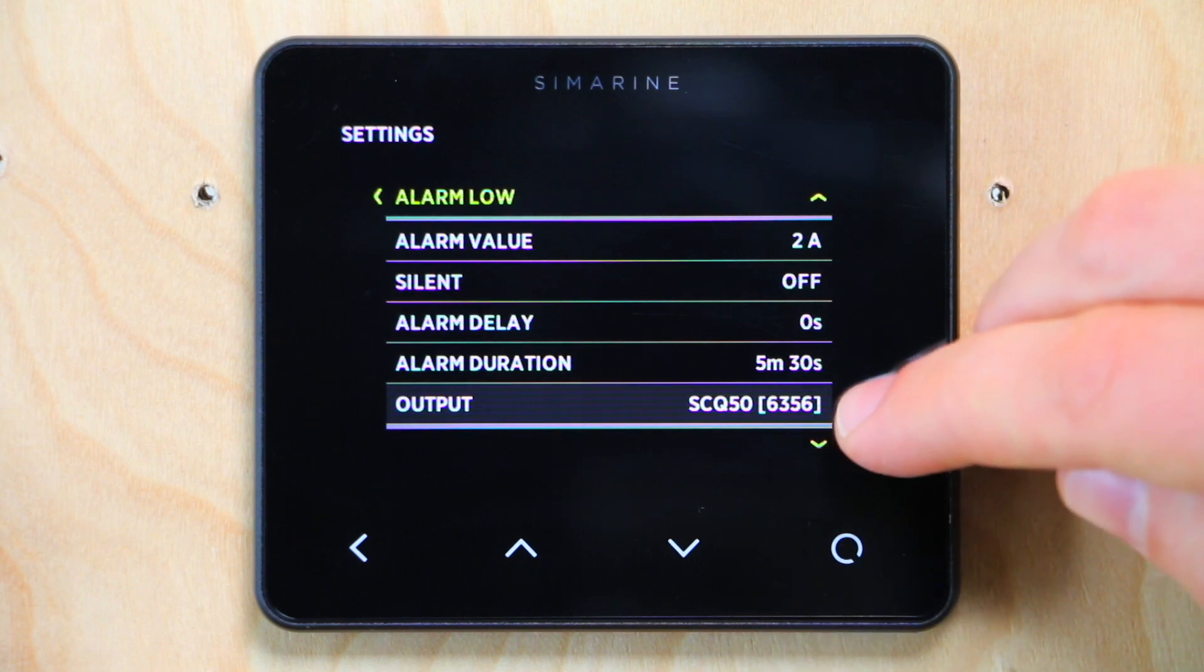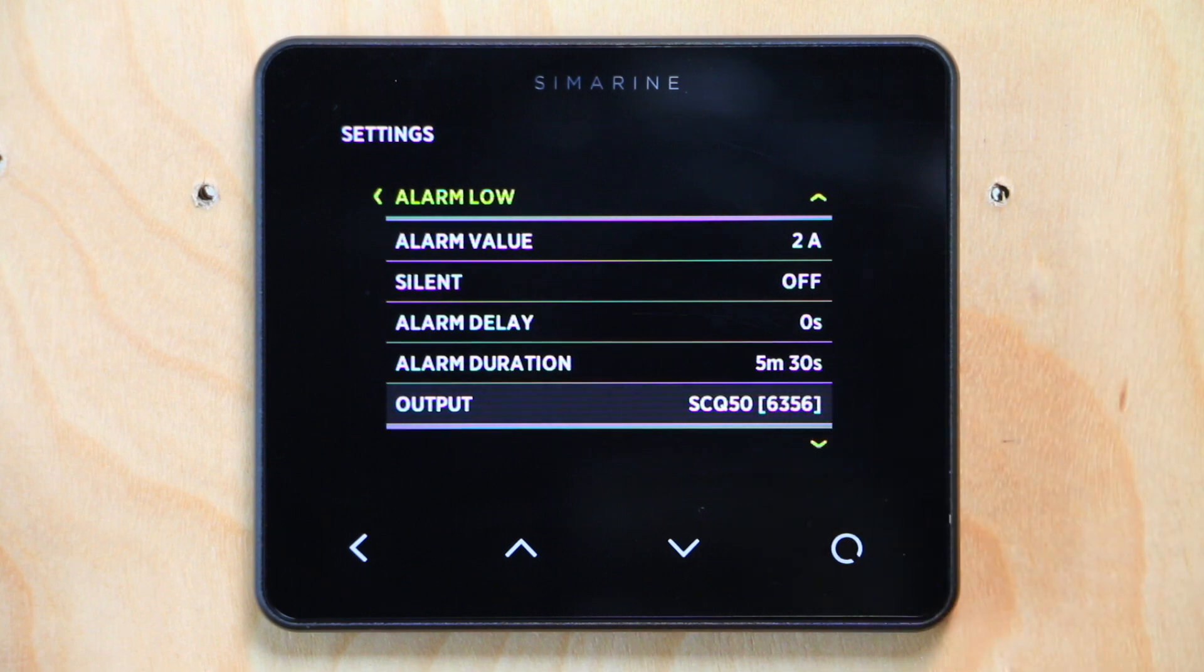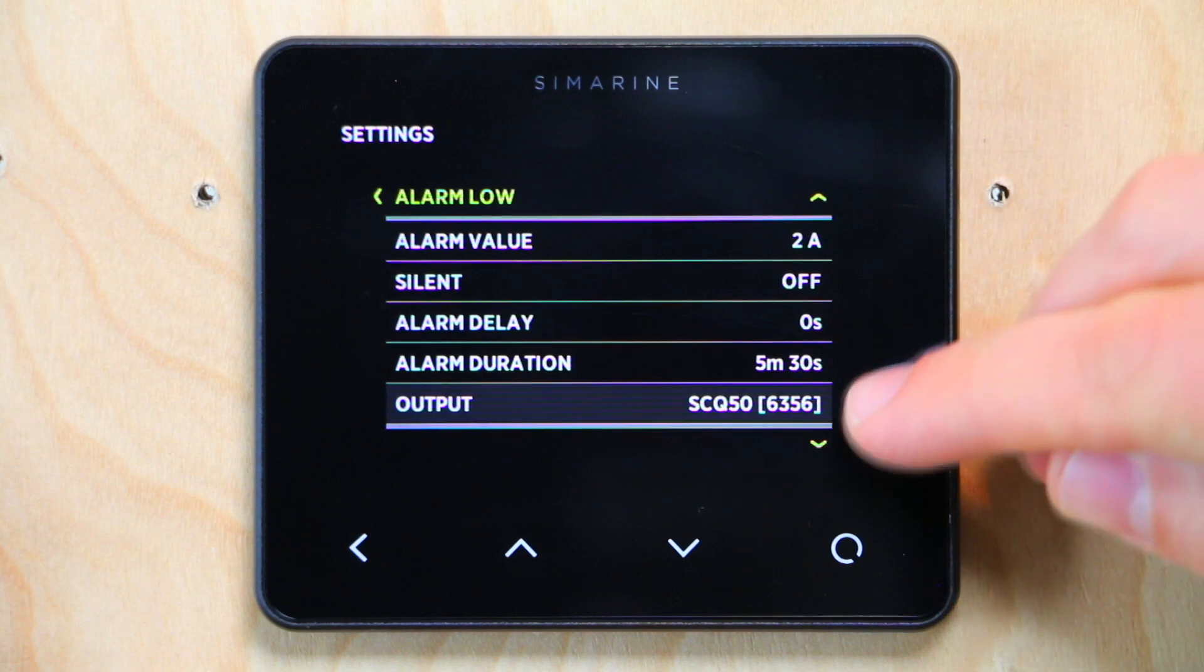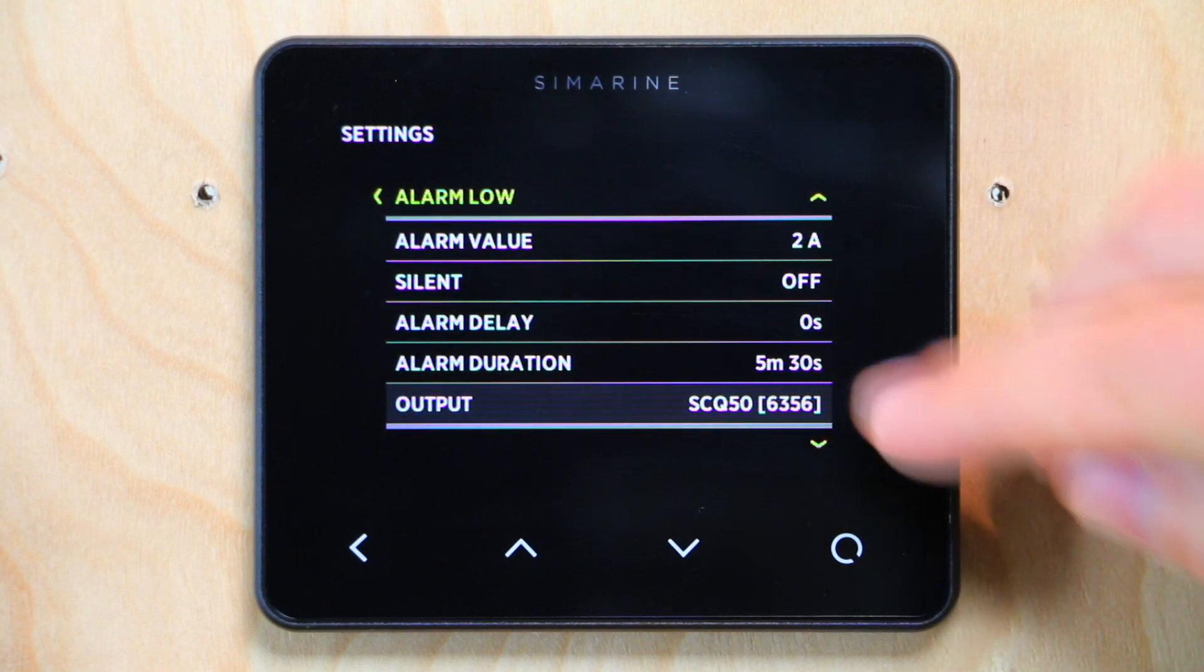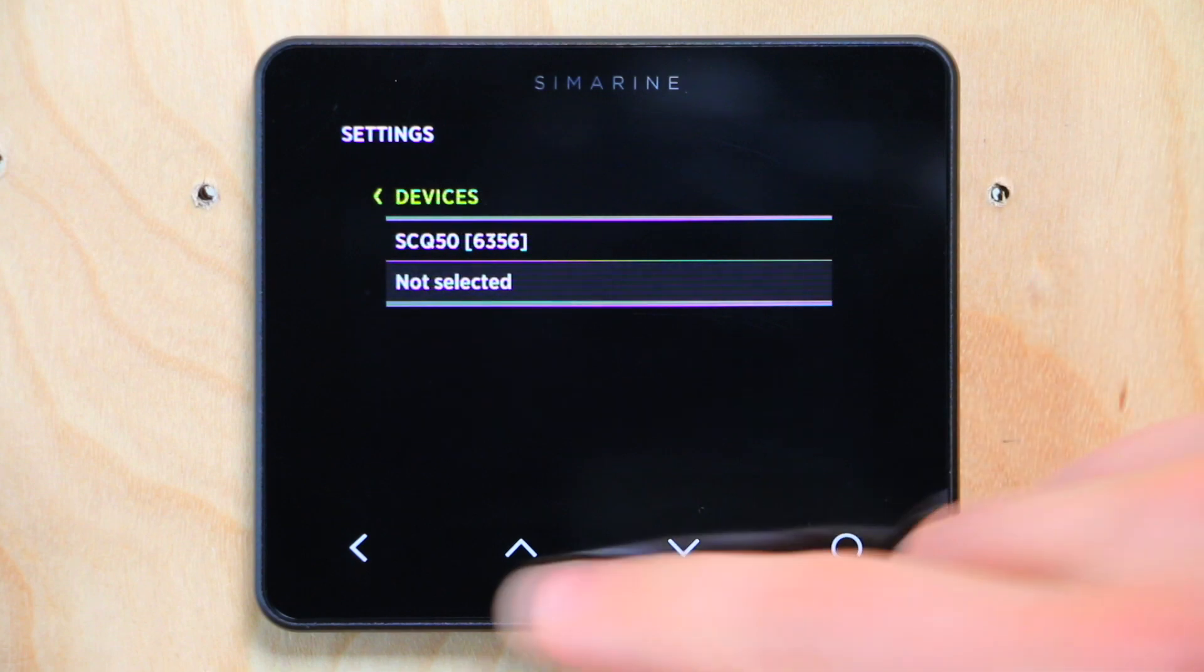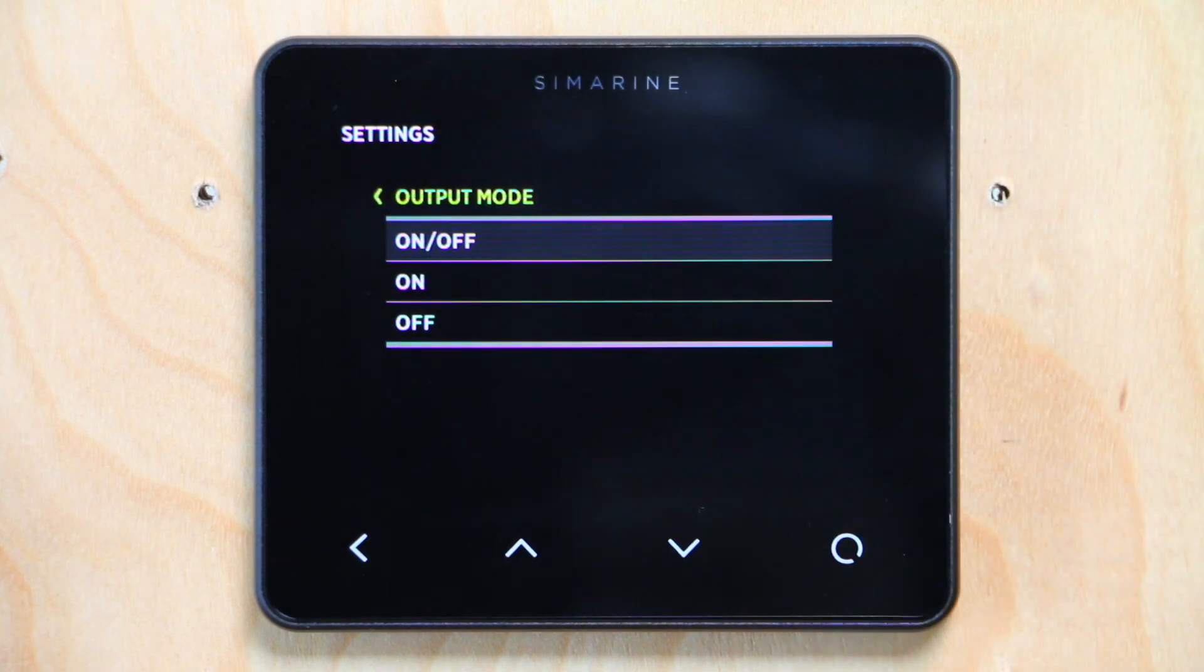The output, this is the output relay on the Quadroshunt. SCQ50 is the Quadroshunt model number. 6356 is part of the serial number for that particular Quadroshunt. That way if you have multiple Quadroshunts, you can grab the serial number and know which one you're selecting. If we had one of the other modules from Simarine, we would select that module. The Quadroshunt is the only one with a little alarm relay on it, but if we had multiple modules plugged in that had relays, all those relays would show up in this list. We've selected the one that's available in this system. And the output mode is on-off.